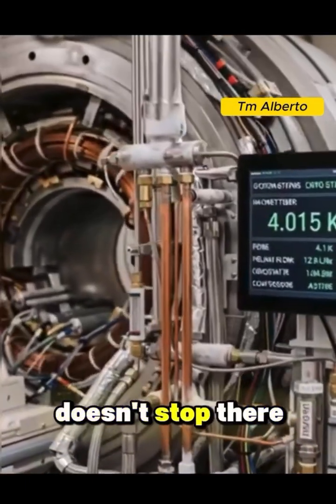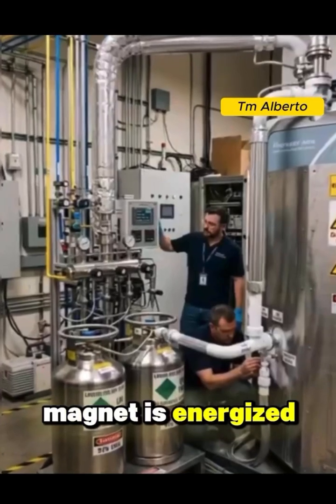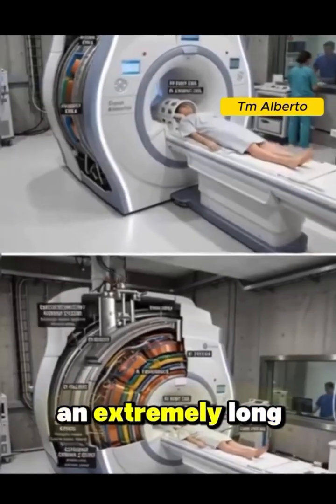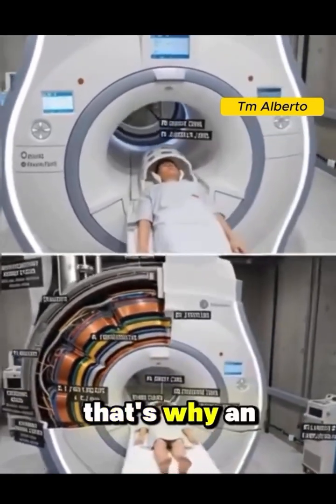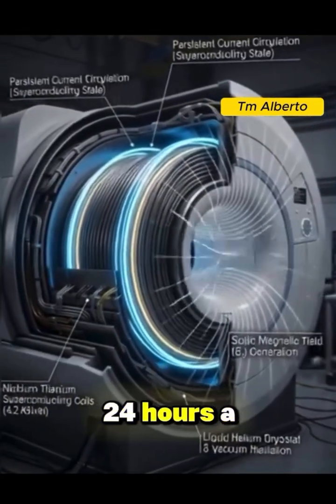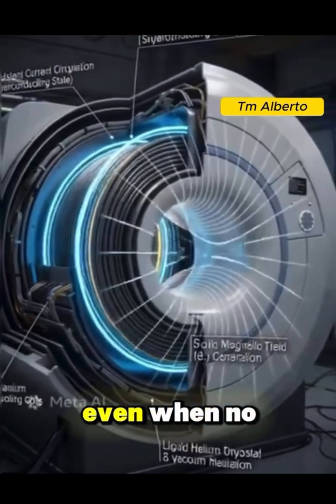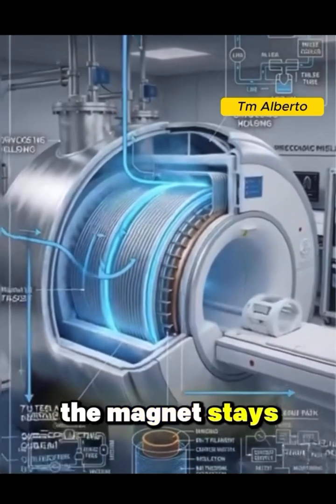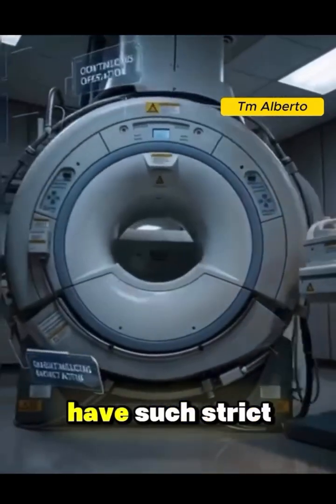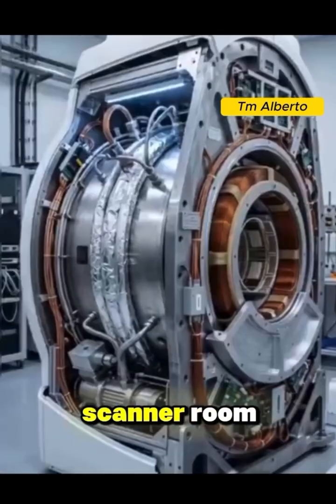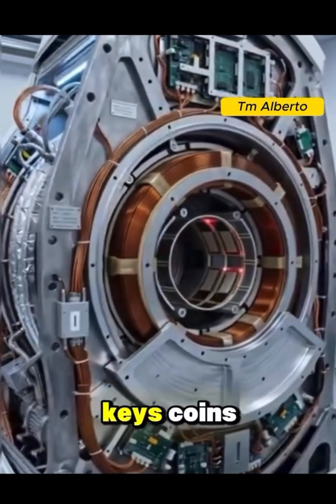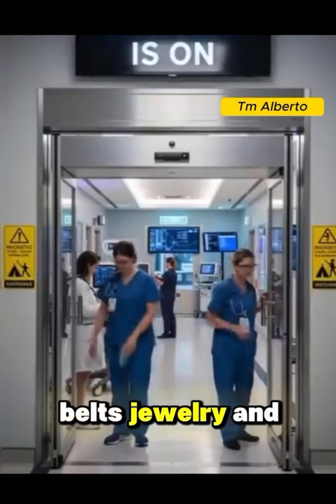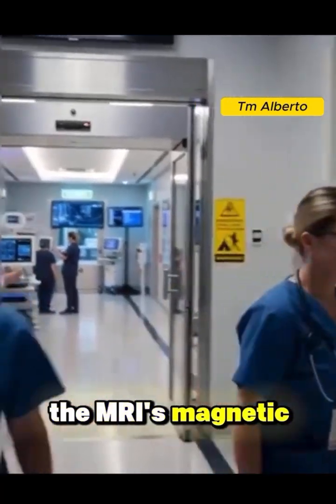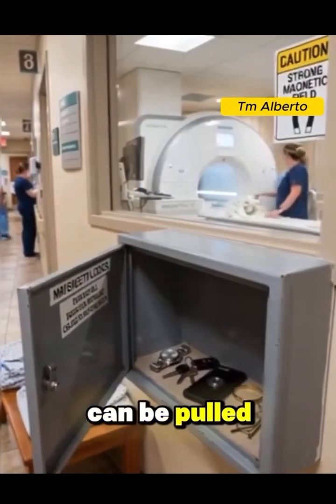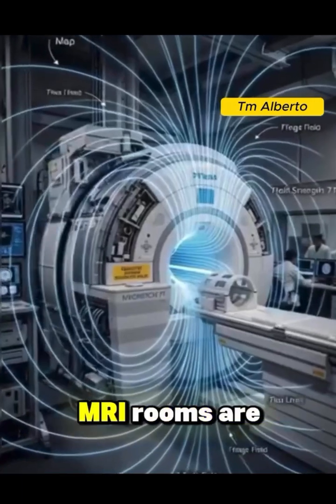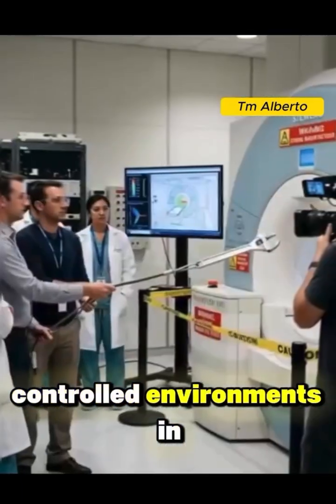And the engineering doesn't stop there. Once the superconducting magnet is energized, the electrical current can continue flowing for an extremely long time without significant energy loss. That's why an MRI's main magnet remains active 24 hours a day, 365 days a year. Even when no patient is being scanned, the magnet stays switched on. This is also why MRI rooms have such strict safety procedures. Before entering the scanner room, patients are asked to remove watches, keys, coins, belts, jewelry, and all other metallic objects. The MRI's magnetic field is so powerful that certain metal objects can be pulled toward the machine with tremendous force. That's why MRI rooms are considered some of the most carefully controlled environments in modern medicine.